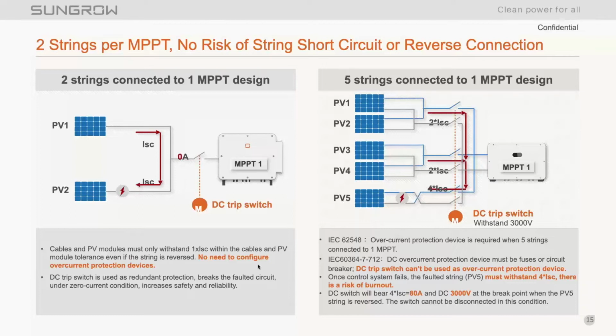So in this instance, that input, PV circuit number 5, has to withstand 4 times the short circuit current. And there is definitely a risk of a burnout, which is code for a thermal event or something bright and flashy and melty, and that's something that we don't like to see. The DC switch there in this particular scenario would have to bear 4 times the short circuit current, which would be roughly 80 amps or so, and potentially could see up to 3,000 volts of DC at the breaking point, if that current is reversed in a ground fault condition. So the switch cannot be used in a scenario like this.